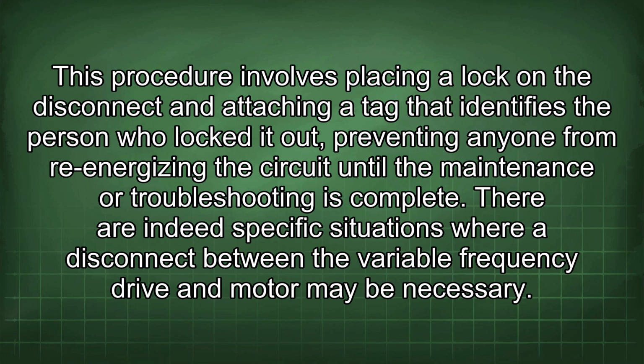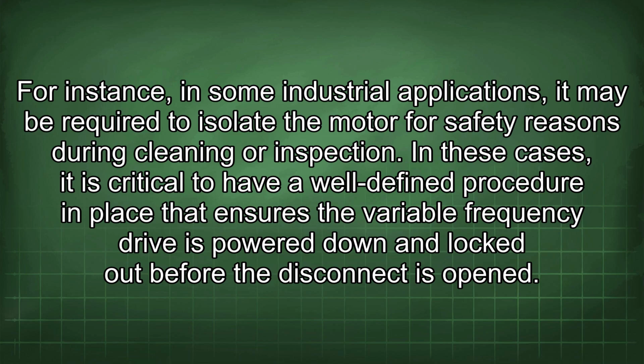There are indeed specific situations where a disconnect between the variable frequency drive and motor may be necessary. For instance, in some industrial applications, it may be required to isolate the motor for safety reasons during cleaning or inspection. In these cases, it is critical to have a well-defined procedure in place that ensures the variable frequency drive is powered down and locked out before the disconnect is opened.